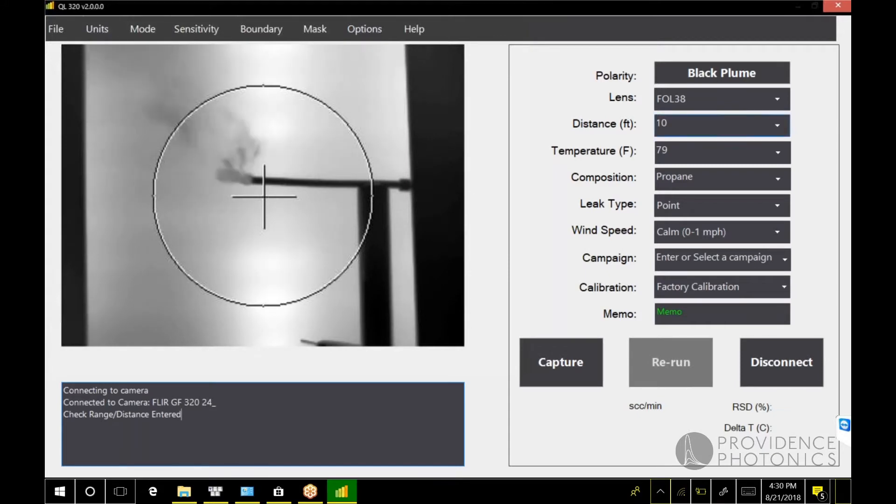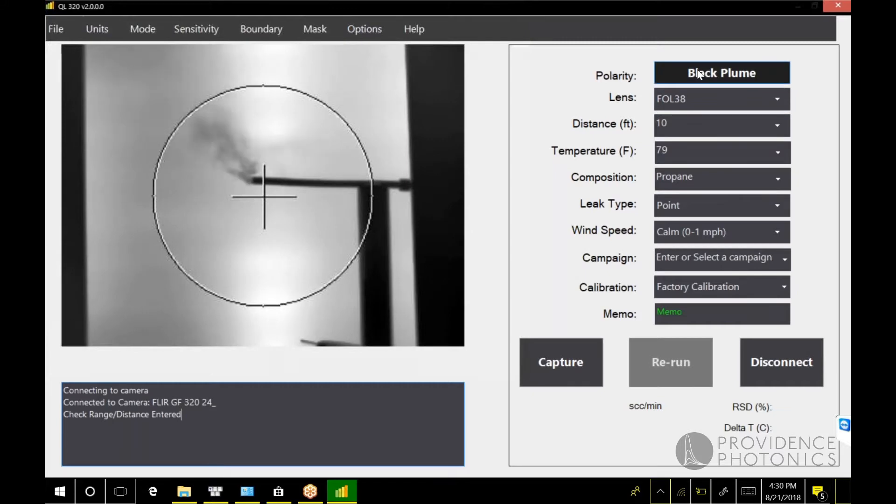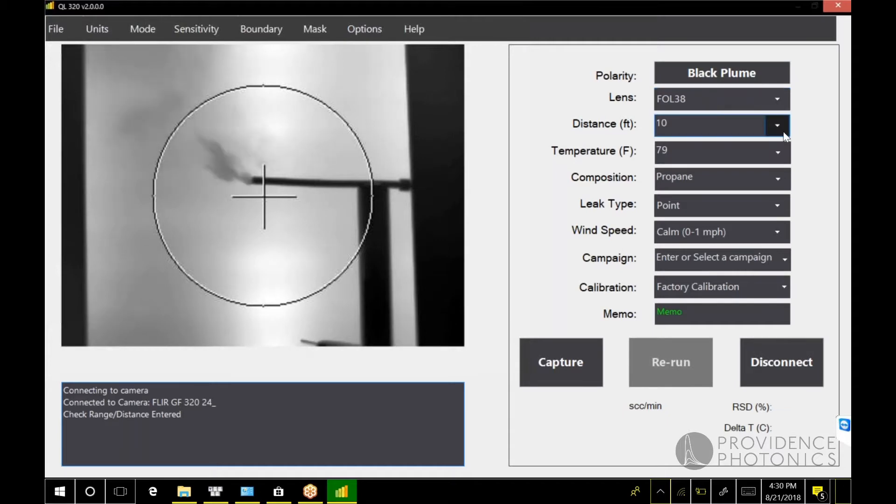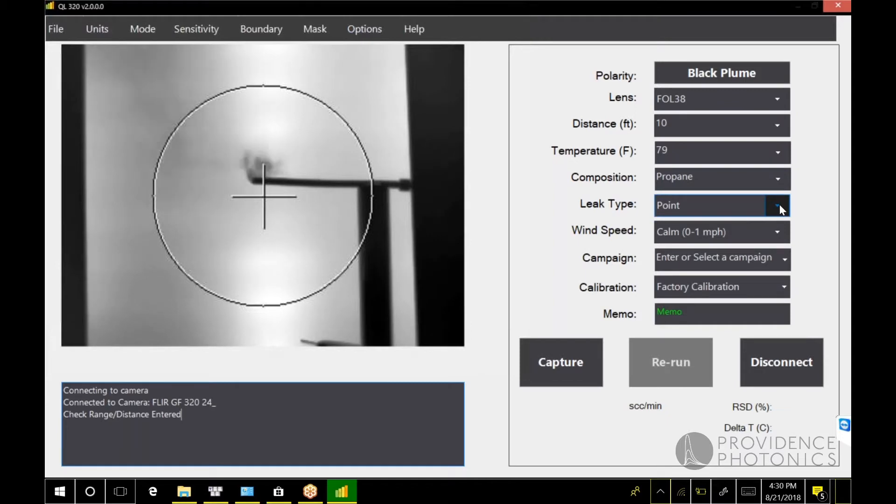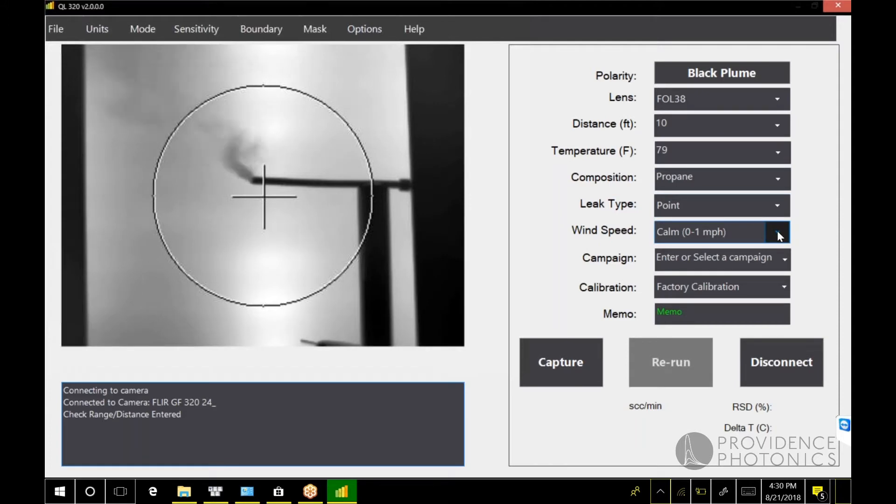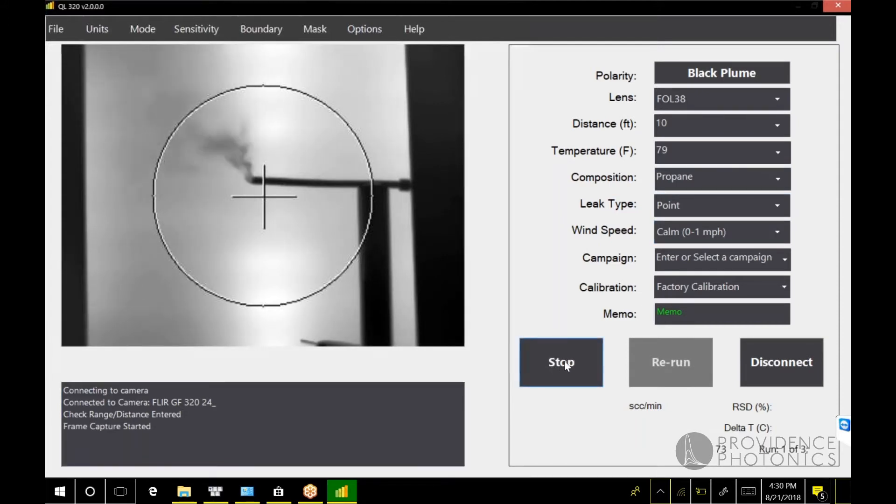Then you enter the information about the leak. You need to tell the QL 320: Is this a black plume or a white plume? Which lens is attached to the camera? The distance from the camera to the leak, the ambient temperature, what type of gas we're quantifying, what type of leak it is, whether it's a point release or a diffuse release, and the wind speed.